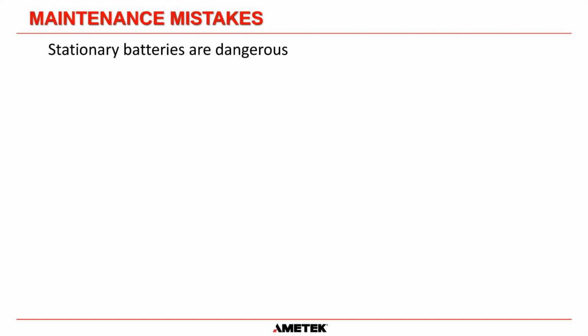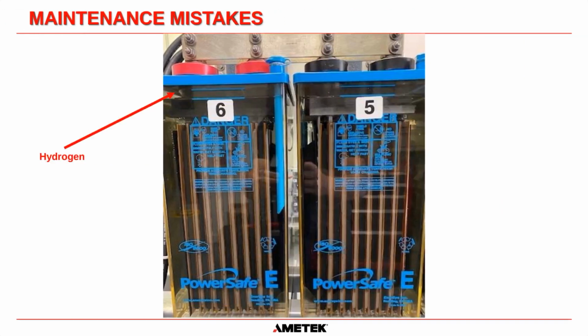Another maintenance mistake is people don't understand that stationary batteries are dangerous. You can see in this cell here, this is the electrolyte level here. So there is an area between here and here, between the top of the electrolyte and the top of the battery lid, that is full of hydrogen. And everybody knows that hydrogen is an extremely explosive gas. Now, in truth, there will be a flame arrestor on the top of the battery. The flame arrestor's job is, if there is any ignition source outside of the battery, that it cannot get back through the flame arrestor into the hydrogen inside the battery and cause a huge explosion. That is, if the flame arrestor is fitted and if the flame arrestor is correct.